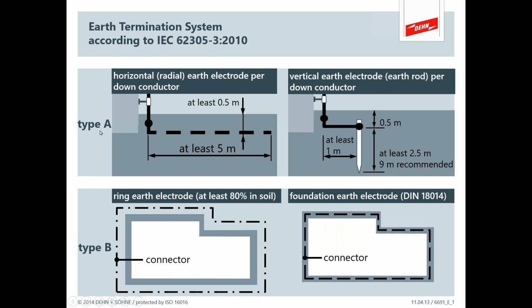So this terminology type A and type B is used to describe what would look like a single earth electrode versus things that are rings or foundation earth electrode systems. Lots of methods to do this that are safe, effective ways to disperse lightning into your earth. It's also really important to remember that your earth termination system at the ground level, the lightning earthing rods, are to be connected to the other earthing rods that are within their influence, and the water pipes and things like that of the system. They should be connected if they're next to them, if they're within the influence of the soil.